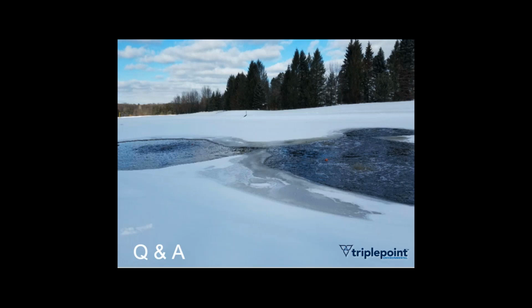If you're going to create an anaerobic area, that's fine. I think you've got to be a little bit careful, because if you get too much sludge, then you start to see a lot of the issues that we were talking about earlier with septicity, odor, popping sludge, etc. It certainly can help to move all the sludge into one place, and that sounds like a really good idea, but it's kind of hard to guarantee as well.